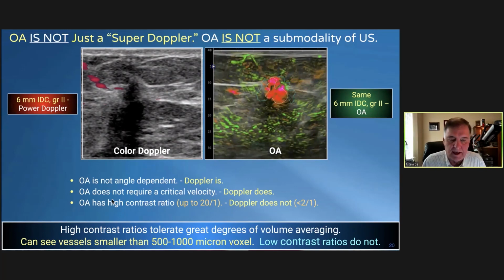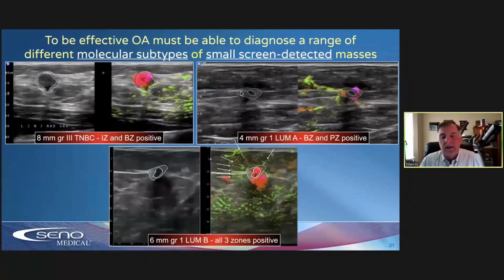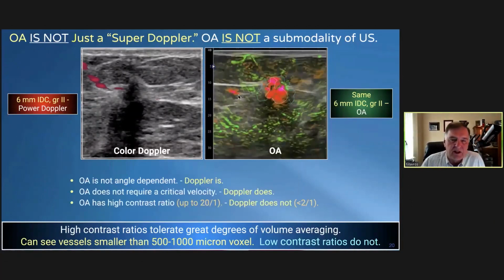And we know from histologic correlations that we often see vessels in the 80 to 100 micron range in the optimal focal zone of the transducer. And then the last thing is that OA shows a relative deoxygenation, which Doppler can't show at all. Now, on the left, both of these are the same lesion. This is a 6 millimeter grade 2 invasive ductal cancer. This is actually a luminal B. And we can just see a single vessel on Doppler, but on OA, there's a deoxygenated blush filling the entire internal zone, a deoxygenated red blush in the boundary zone, and multiple green radiating vessels. So that degree of discordancy between what Doppler shows and OA shows is not at all unusual.